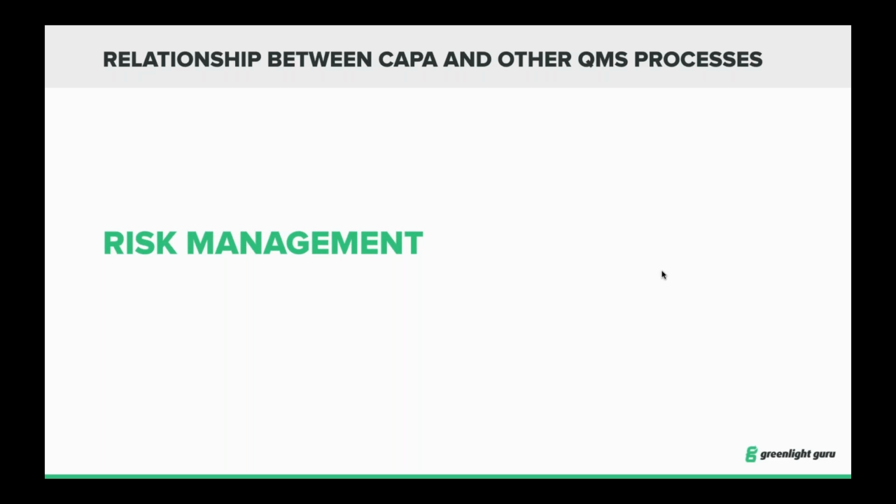Risk management. Oh man, this is such a deep topic on a number of fronts. With respect to design and development of medical devices, there's certainly a strong emphasis put on risk management at those points in time, as defined in 14971, which, by the way, about a year ago had a revision published, the 2019 version. So if you haven't, be sure to check that out.